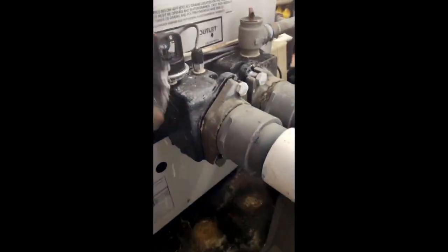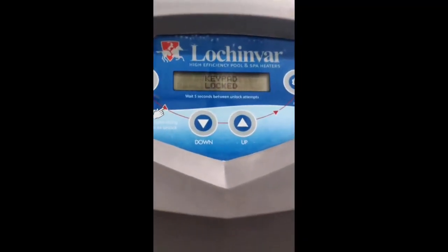I will know, and if it is not auxiliary device 1, then I will have to try this sensor here, which is an inlet sensor or outlet sensor, no, inlet, and then I got a high limit sensor on there as well, and I'll have to go to those other things because it kind of threw me for a loop. But you see that thing burning through that sight glass. That's what we want to see. We want to stay in operation.